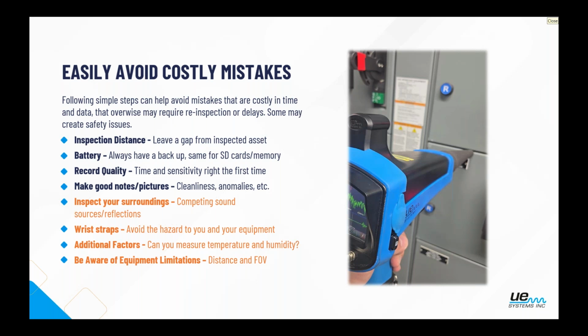And then the other point too, if we're doing electrical inspection, there are other factors you might want to consider. Are you able to document the temperature and the humidity of the room? If there's high humidity in an MCC room, that's definitely an issue. But really where we're looking for that is anything that's in a non-climate controlled environment. Humidity can play a factor, and it should be something that we're in consideration of.